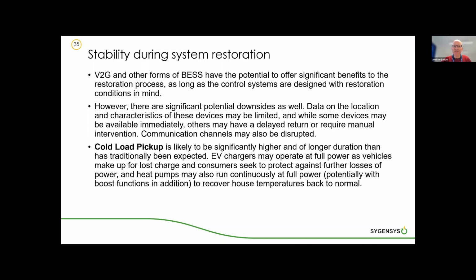And also, Andrew touched on the issue of cold load pickup earlier. This is likely to be significantly higher and of longer duration than traditionally been expected. So EV chargers may operate at full power as vehicles make up for lost charge, and consumers seek to protect against further losses of power.